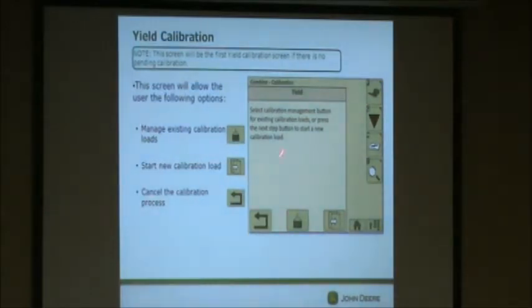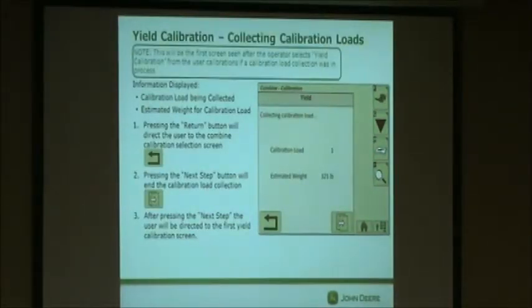Here's where you're going to manage your calibrations. And you're going to start a new calibration load. So in order to do that, we're going to push this button down here on the bottom right. And then we're going to see here that we're calibration load 1. Now, in order to get a calibration load, we've got to have a minimum of 3,000 pounds. The more, obviously, you're going to get a better calibration.